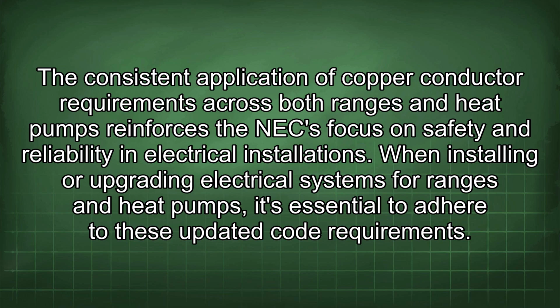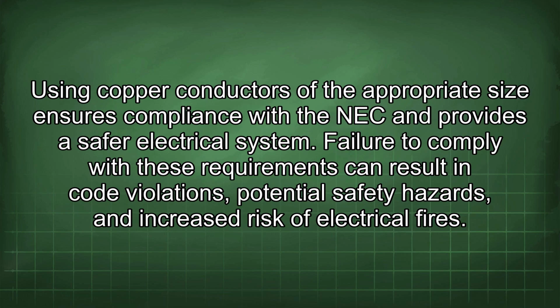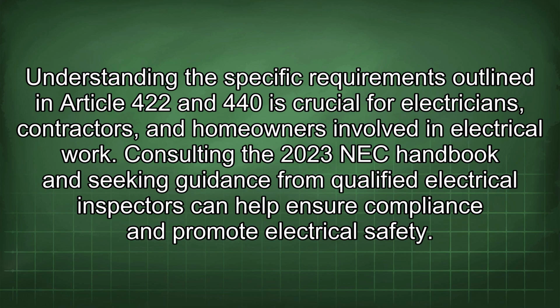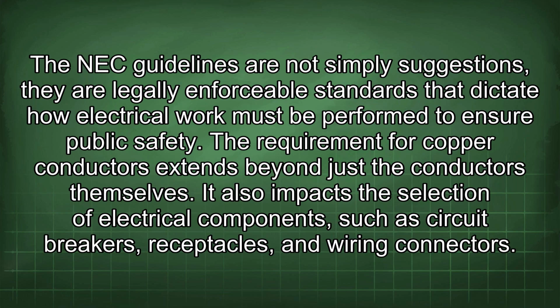When installing or upgrading electrical systems for ranges and heat pumps, it's essential to adhere to these updated code requirements. Using copper conductors of the appropriate size ensures compliance with the NEC and provides a safer electrical system. Failure to comply with these requirements can result in code violations, potential safety hazards, and increased risk of electrical fires. Understanding the specific requirements outlined in Article 422 and 440 is crucial for electricians, contractors, and homeowners involved in electrical work. Consulting the 2023 NEC Handbook and seeking guidance from qualified electrical inspectors can help ensure compliance and promote electrical safety. The NEC guidelines are not simply suggestions, they are legally enforceable standards that dictate how electrical work must be performed to ensure public safety.